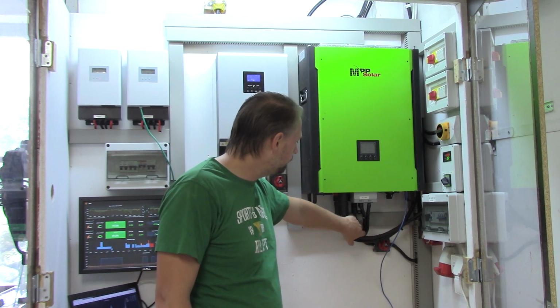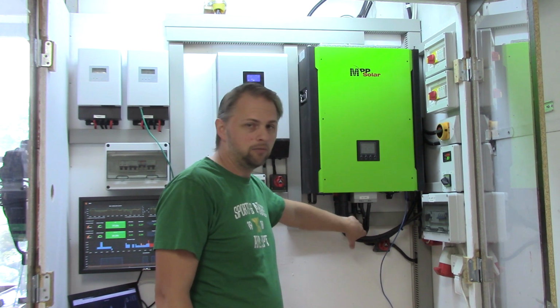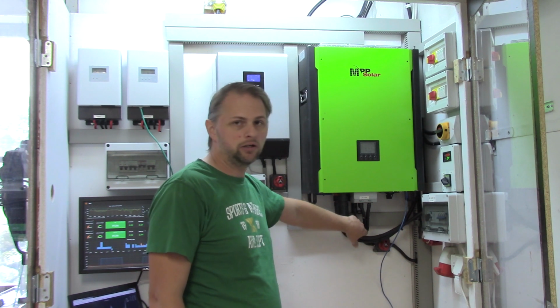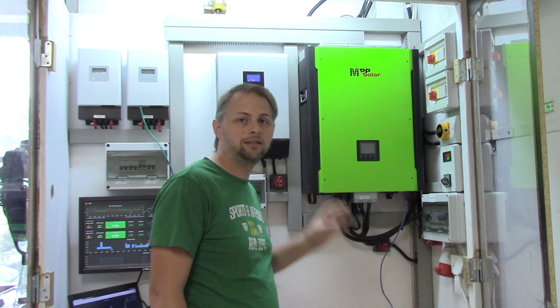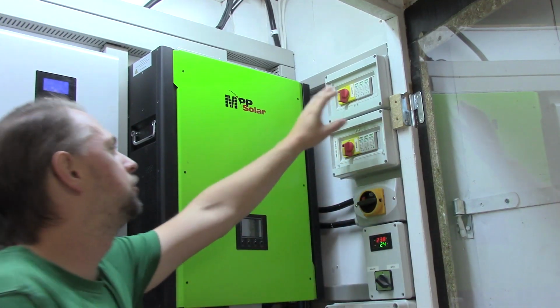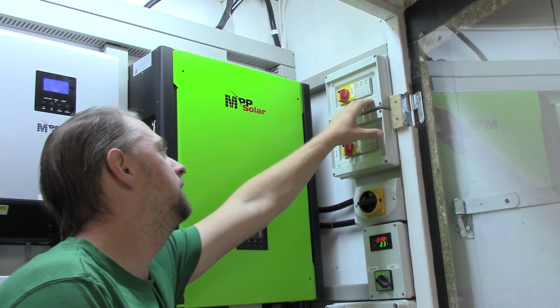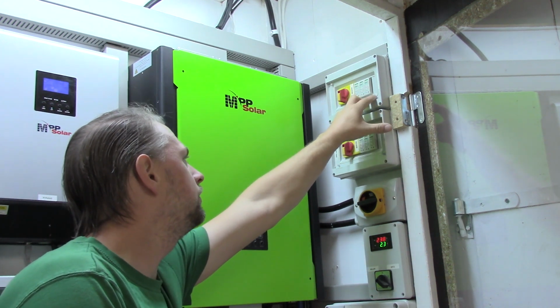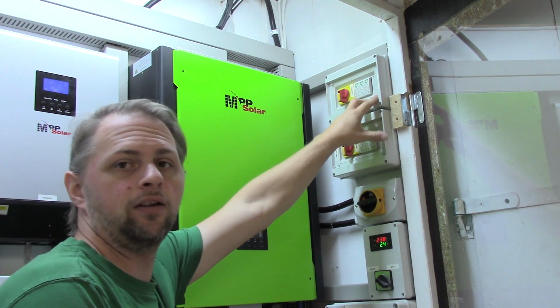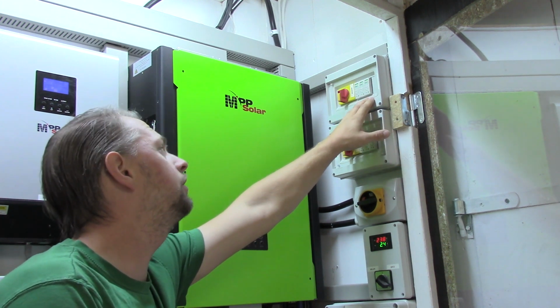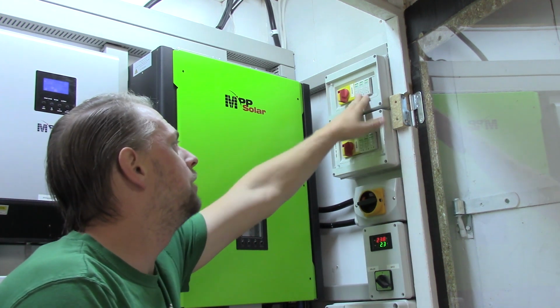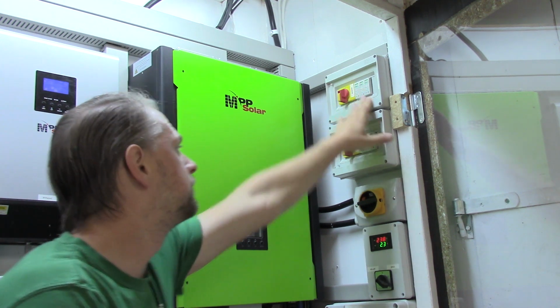This one is running high voltage PV. That means I'm going with between 500 and 700 volt DC. We start from the top here. We have the first PV incoming here, and this is the one going to the west. I have 18 panels on this one in series. We have the breaker and we have the lightning protection here.